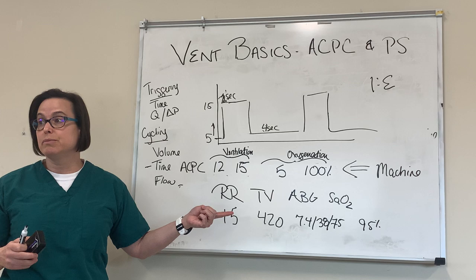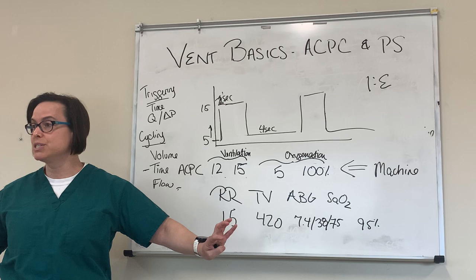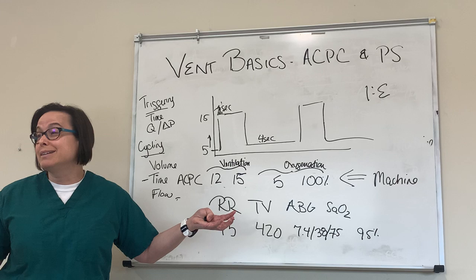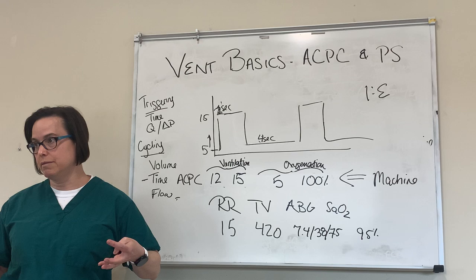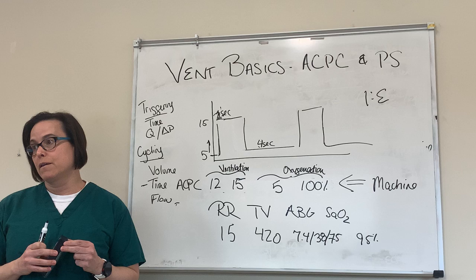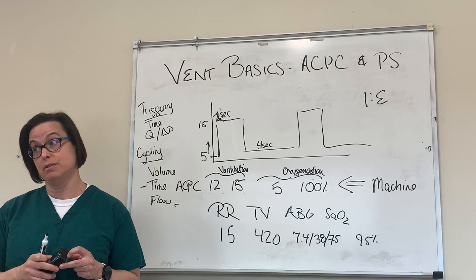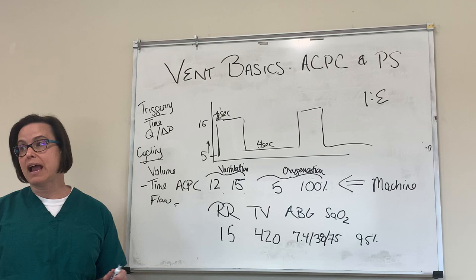That's why I really like ACPC — that easily manipulatable I to E ratio. The reason it's going to be really helpful if we have to hook patients up to one ventilator — probably about four patients max, and we don't want to do that, there are a lot of reasons not to, but if it's a last ditch effort we might — is that if we set a tidal volume, we wouldn't know which patients are getting it. If we set a pressure, that's easier to understand, though we still can't measure tidal volume specifically for each individual with one ventilator.